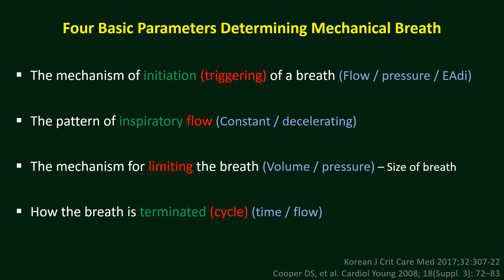Then is Flow — the pattern of inspiratory flow — how much flow will be delivered and what pattern: whether constant flow during the whole inspiratory time or a decelerating flow. Then is Limiting the breath — the mechanism limiting the size of the breath — how much the lung will be expanded during inspiration, to a certain volume or to a certain pressure. And finally, Cycle — the termination of breath — how inspiration will be terminated: after a certain period of time or after delivering a certain amount of flow.